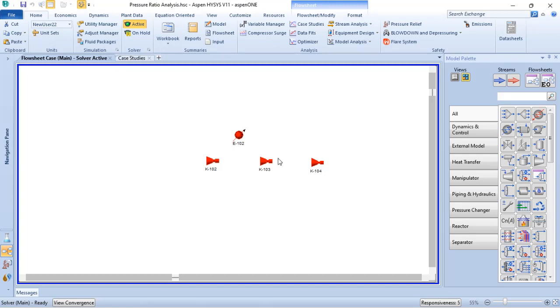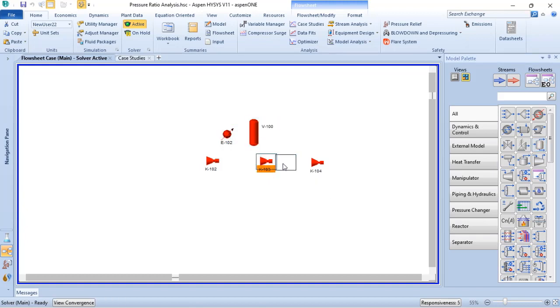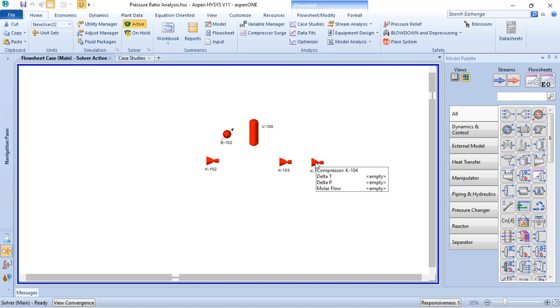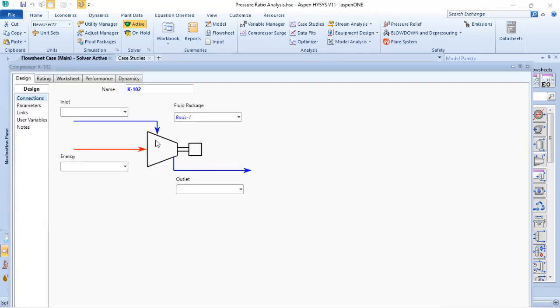Another thing to consider is that when you cool the compressed gas, you can have condensate formation. If that is the case, you need to add a separator to guarantee that the next stage of compression receives no condensate. If HYSYS detects condensate at the suction of the compressor, a warning will be given. The basic setup for simulating a multi-stage compressor in Aspen HYSYS requires inlet and outlet material streams, the energy stream for the compressor, the polytropic or adiabatic efficiency, and the discharge conditions in terms of delta P, pressure ratio, or discharge pressure.